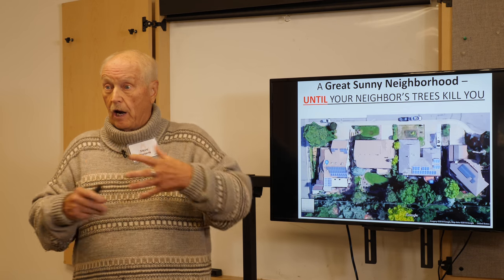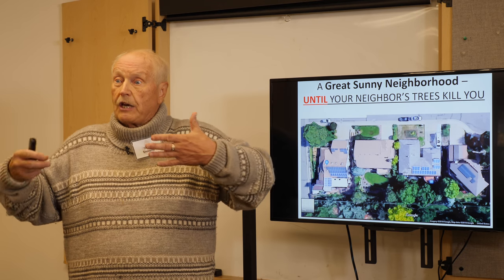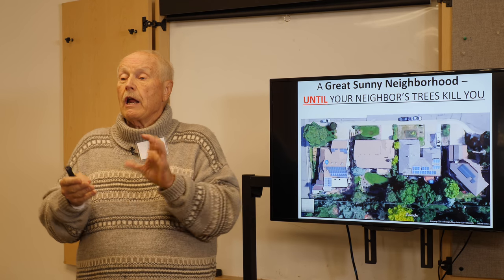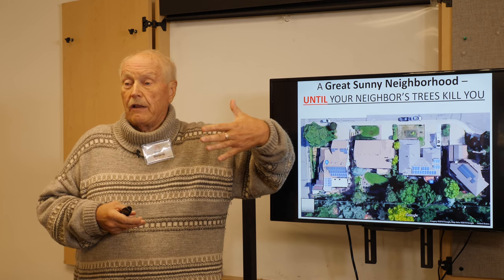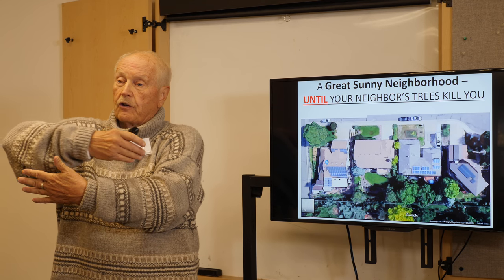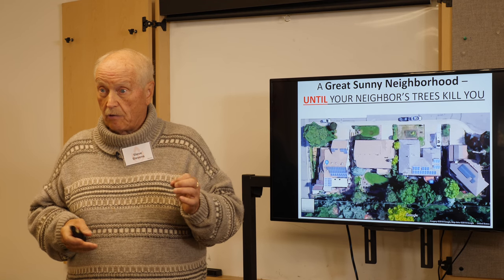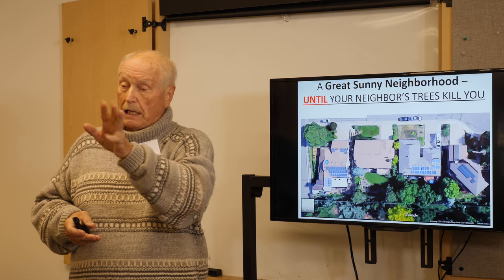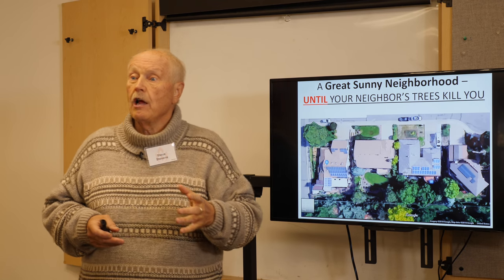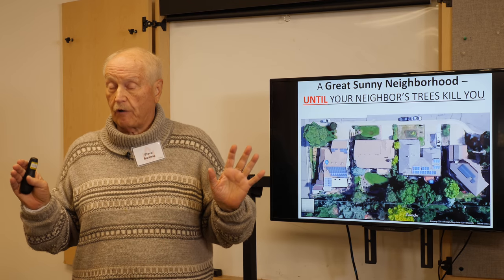taking out inside air. And just like Kim Jong-un and President Moon of South Korea, they shake hands as they pass in this ERV. And so the heat that was in the house air going out is transferred in that handshake to the air that's coming in at about a 95% exchange rate. And the humidity too with an ERV, not with an HRV, heat recovery ventilator. You can change the volume of airflow, and so you have really good fresh air.